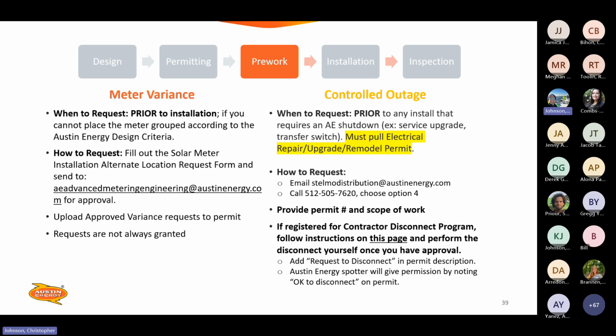All right, the meter variance. You must request this prior to installation. If you build everything and realize you need this, it will most likely be denied. So fill out the solar meter request installation alternate location request form and send it to AE Advanced Metering Engineering at austinenergy.com for approval. Usually they'll send someone out to take a look and they'll get it taken care of. Upload that approved meter variance form to your permit once you receive that. Requests are not always granted. Sometimes they give them, sometimes they do not.